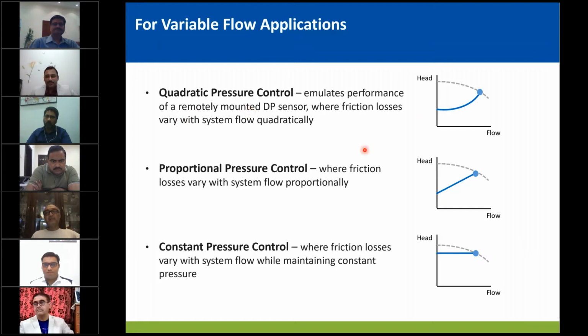Now, coming to the control of variable speed pumps. You have three different control curve opportunities. The most energy saving option, or the best practice, is a quadratic control curve that connects the design point and the set point, the minimum head to be maintained in a system. As we saw, if you put a remote DP sensor and properly set it, we will probably achieve this control curve.